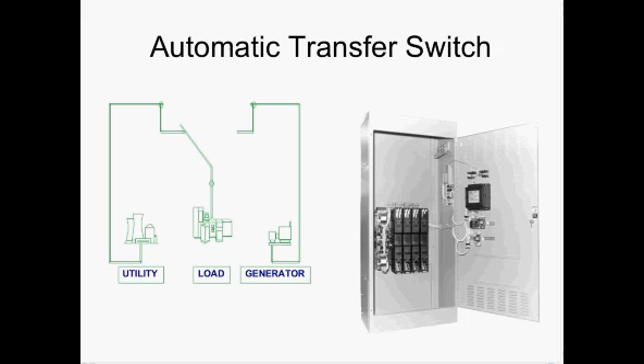Both of these components are designed by the respective manufacturers to stringent industry standards to obtain an acceptable level of reliability. The manufacturers must ensure these components for their respective systems meet the applicable standards. These transfer switch and engine generator sets then must be installed per the applicable codes and standards and inspected, tested, and approved by the authority having jurisdiction before being commissioned for operation. When the standby power system is installed brand new, it is as reliable as it can be. To maintain reliability, it must be maintained on the manufacturer's recommended schedule. In some cases, there are regulatory agencies that dictate regular inspection and testing schedules for the emergency generators. If they do not get regular inspections and maintenance, they will not remain reliable.